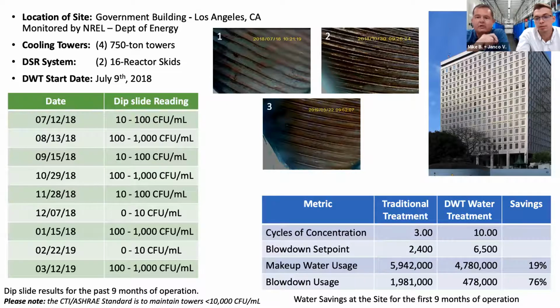It's not only doing a better job at scale control, as you can see in images 1, 2, and 3. Image 1 is right before we started, a borescope image inside their chiller, which is the heat exchange surface. The second image is 3 months later. Bill Brady, the chief engineer at LA City Hall, borescoped it, and his jaw was on the ground. He said, 'Well, where did my scale go?' I said, 'Bill, over time we actually removed scale from heat transfer surfaces.' He borescoped it again 6 months after that, and every 6 months since we've been borescoping the chiller tubes, and they've been spotless, immaculate. So we've achieved theoretical perfection on the heat transfer surfaces, which chemicals just frankly can't do.